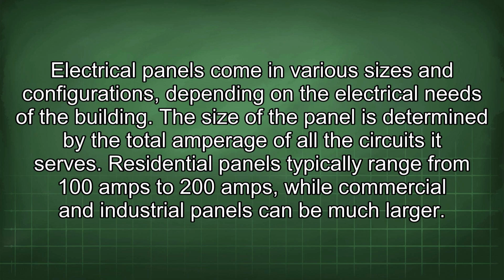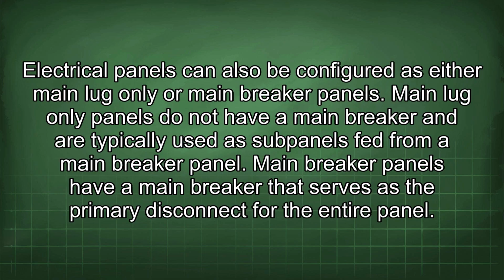The size of the panel is determined by the total amperage of all the circuits it serves. Residential panels typically range from 100 amps to 200 amps, while commercial and industrial panels can be much larger. Electrical panels can also be configured as either main lug-only or main breaker panels. Main lug-only panels do not have a main breaker and are typically used as sub-panels fed from a main breaker panel. Main breaker panels have a main breaker that serves as the primary disconnect for the entire panel.